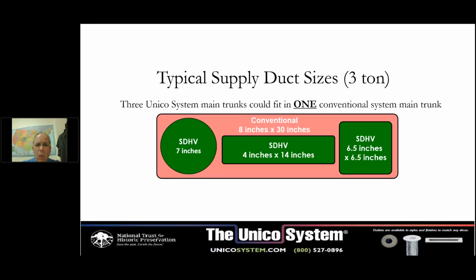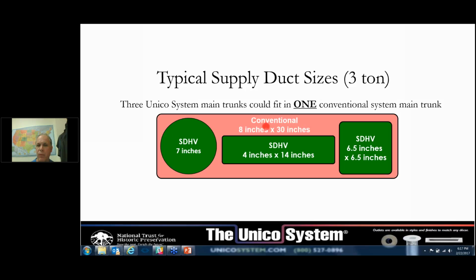One of the great things about the small duct systems is that they're small. I showed you that main trunk before — the area in pink here is an actual conventional main trunk, generally sized 8 by 30 inches. You could literally fit the trunk lines of 3 different small duct systems within that space. So if you just have the one system, it would take up only 1/3 of the space.